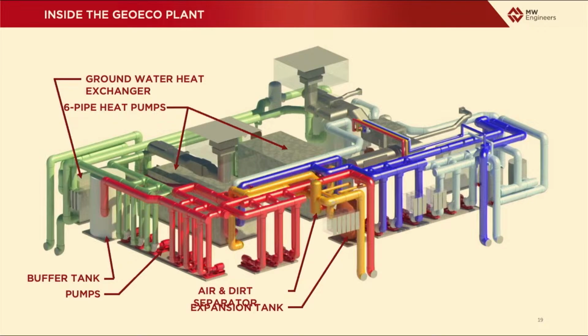And then from there, they're moved throughout campus through large piping distribution systems. The dark red pipe is the hot heating water, so that's the water that goes out to a building and heats the building. It releases energy into the building, and the water comes back at a lower temperature in the orange pipe and is reheated with these 6-pipe heat pumps. The blue pipe is cold water, so it leaves the building, goes out and cools buildings. Energy is added to that cold water pipe and comes back warmer, and that's the light blue pipe, and it's recooled through the heat pumps.